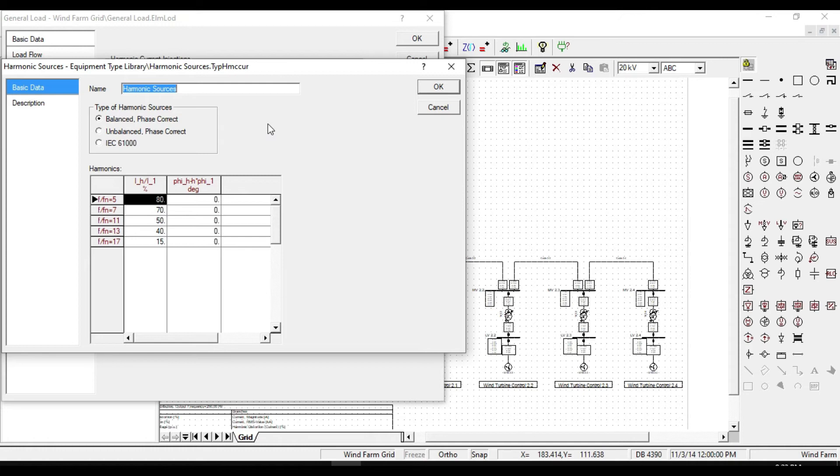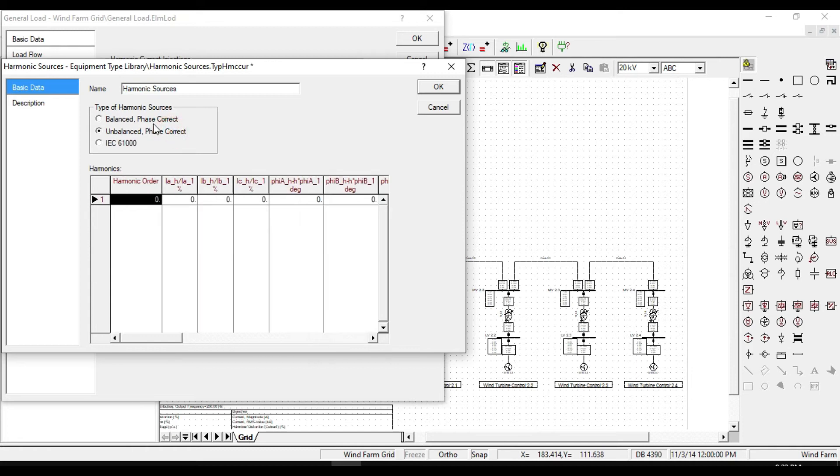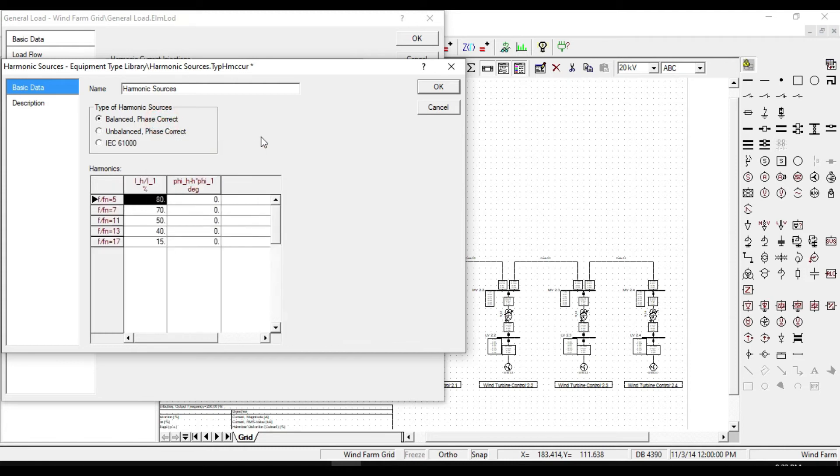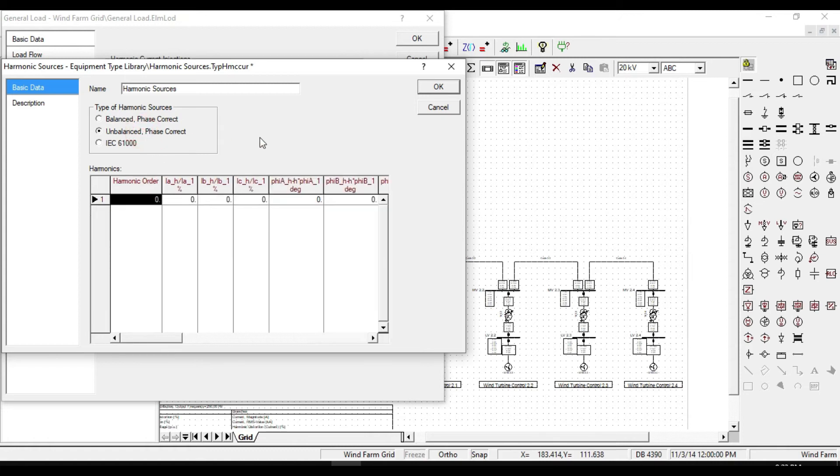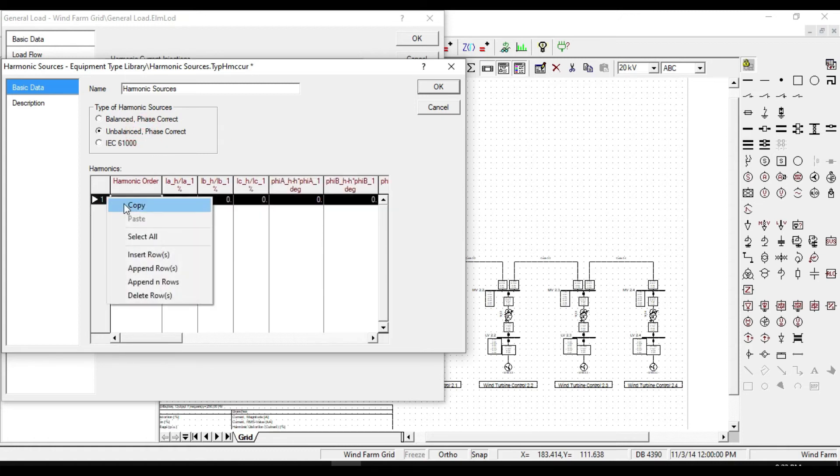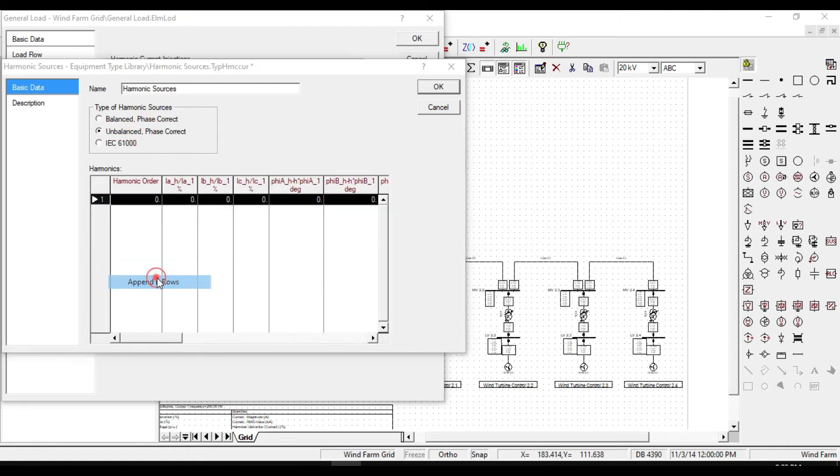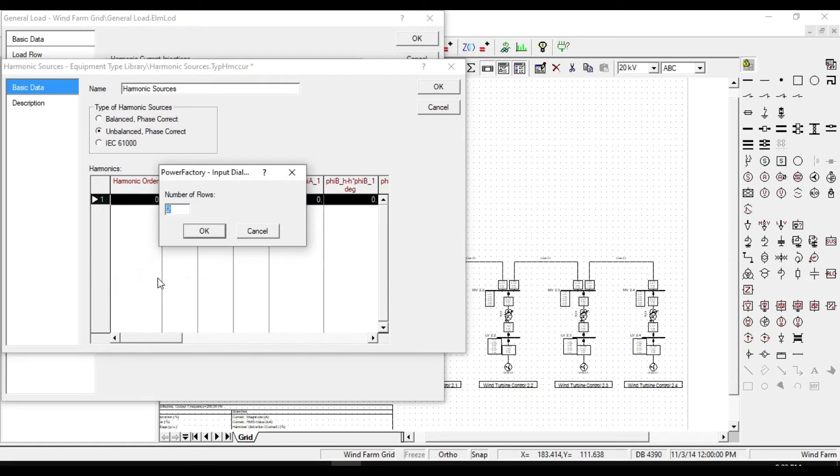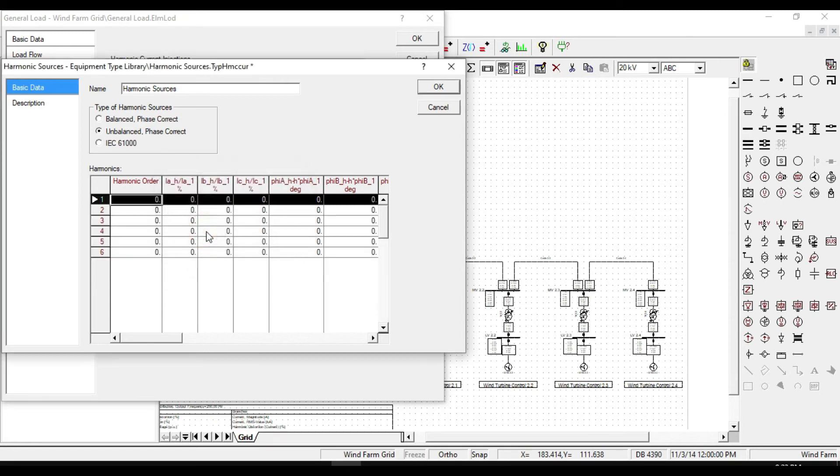If we define the type of our load as unbalanced, then we will see both the third and also even harmonics in our system. Select unbalanced phase correct, then define the harmonic orders. Here you can define whatever order of harmonics you want.